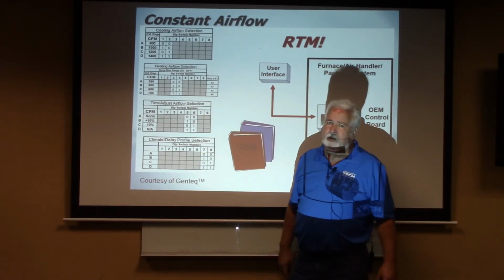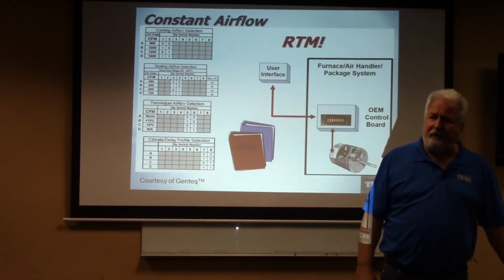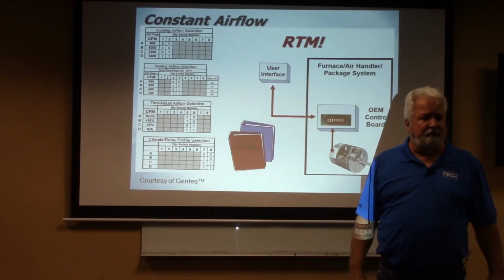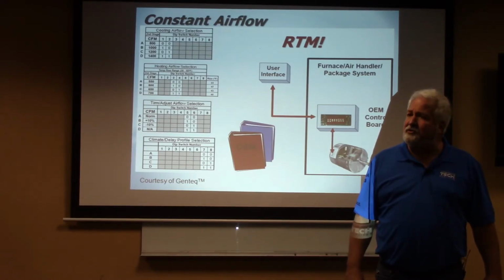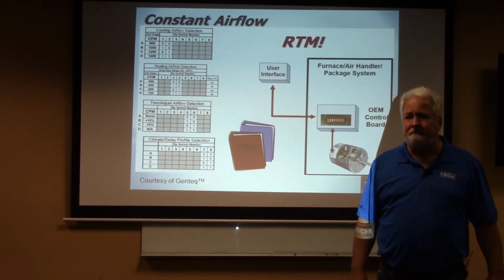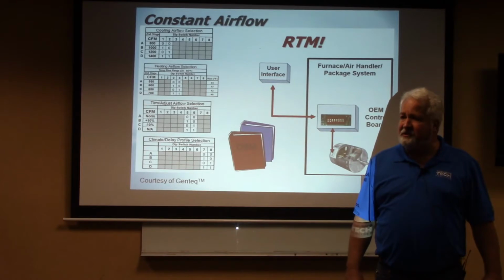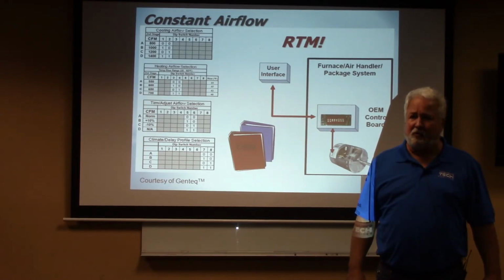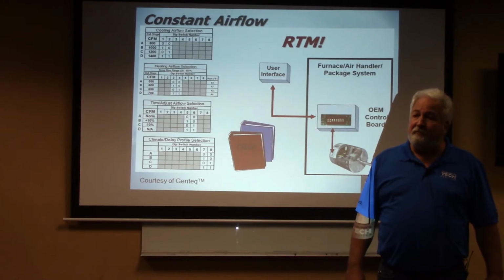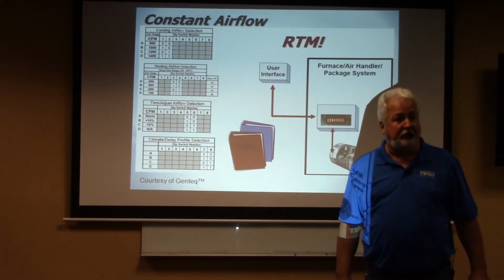Your climate delay profile, that's going to be, do I want that system to stay running after the air conditioner shuts off? Do I want the fan to stay running? If the fan stays running when that system shuts off, is that coil still wet? It's still wet. So if the fan stays running and it's blowing across a wet coil, what did you just do to the house? Add the humidity back in there that you just took out. So when we're dealing with variable speed motors, we want what to happen on our motors in our marketplace? When that system shuts down, what do we want to do? Shut the fan off, okay? So that's where this climate delay profile comes into play.